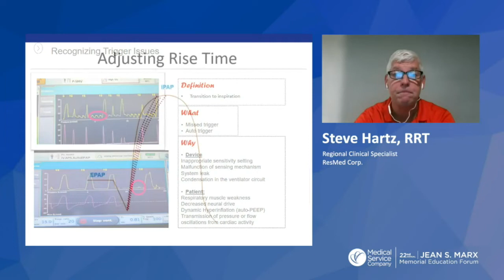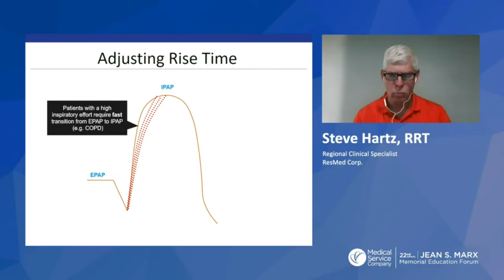We move into adjusting rise time. I equate that to how fast the air comes in, or how slow, or the peak flow setting on a ventilator. Can I hear good air moving in or not? Or the patient says it's coming in too fast or too slow. Most often you'll see COPD patients requiring a faster rise time. Think about the way they breathe normally: short inspirations, quick, decent tidal volumes, but we have to worry about what happens on the back end. So they might enjoy faster rise times or quicker air. "I want more."